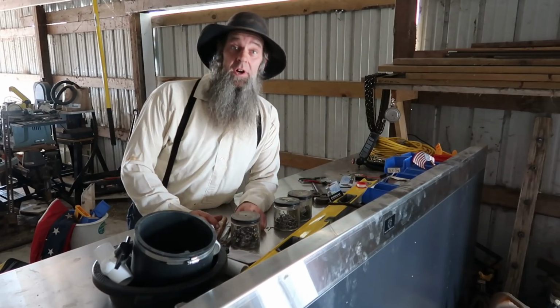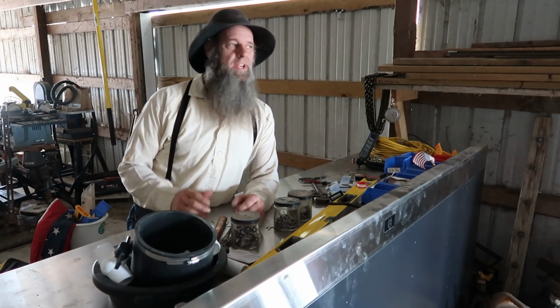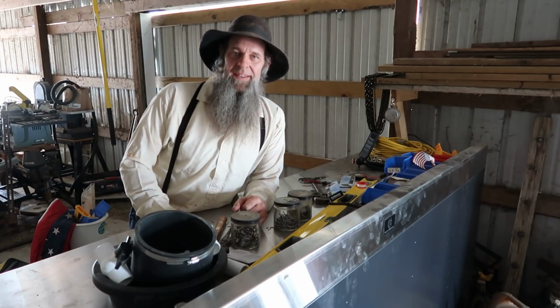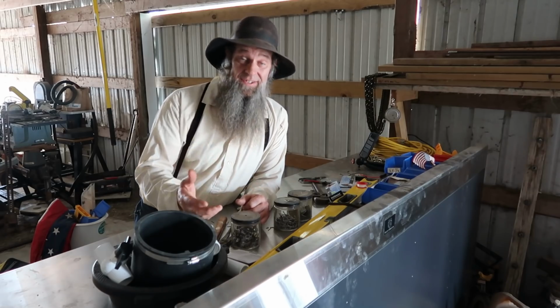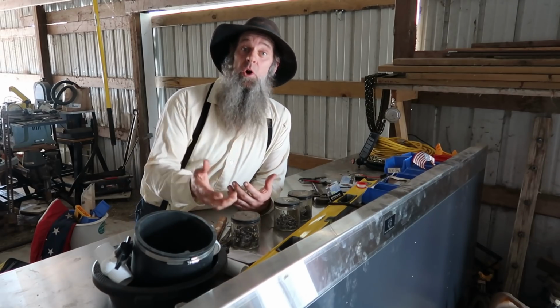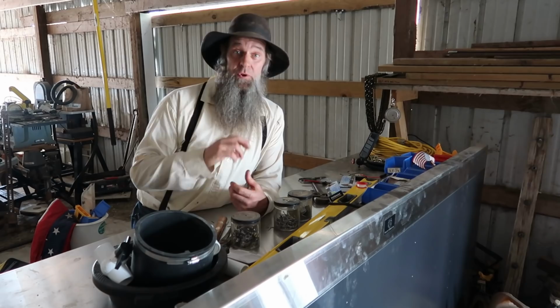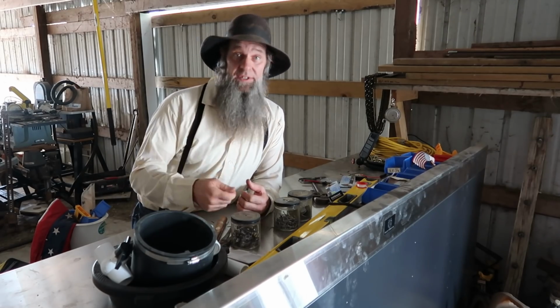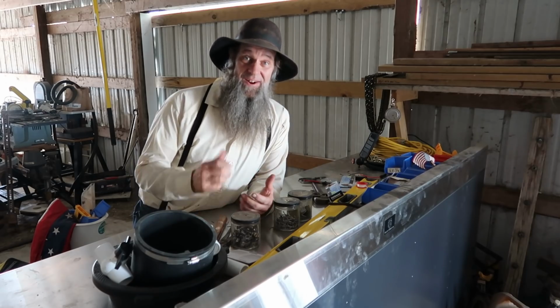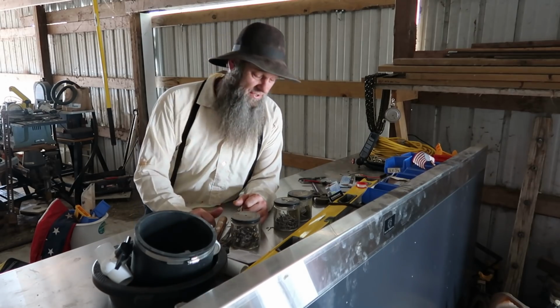And the other thing that you guys talked about was the tape. I used the regular Teflon tape they use for plumbing. That's not recommended for application with corrosive gas. So you wanna use a corrosive-resistant type of tape for your threads when you're threading everything together. So I'll be taking off the pump and replacing the tape on the threads there. So thanks for that suggestion too.